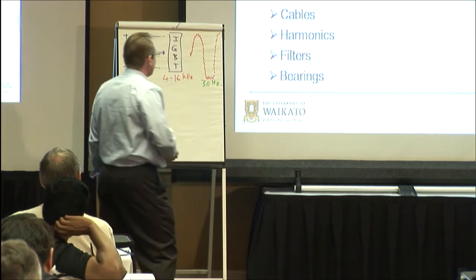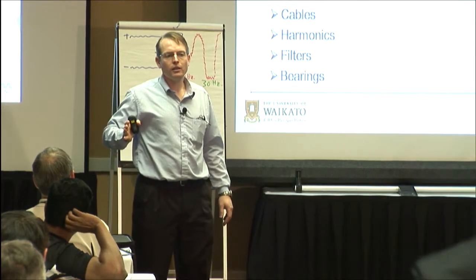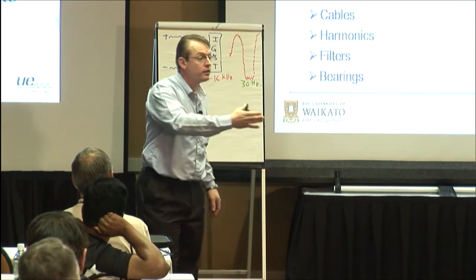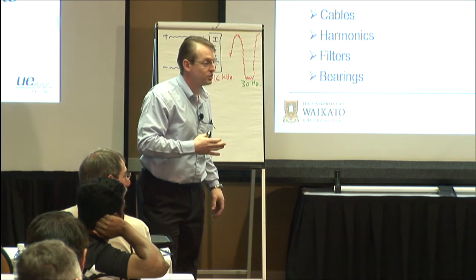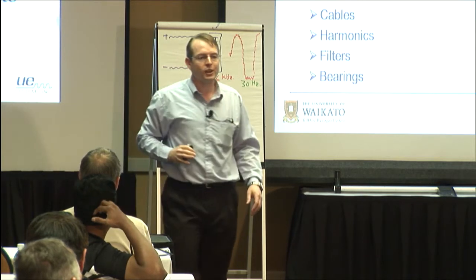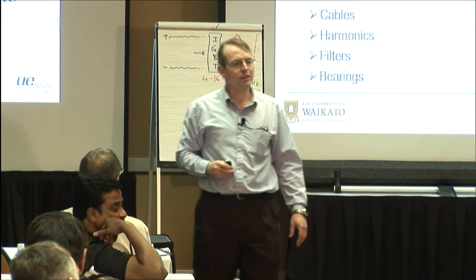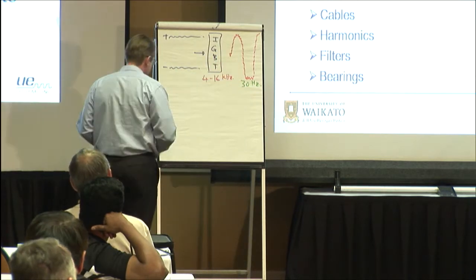As I mentioned, cabling to the VSD, absolutely important. What sort of cables need to be used? Does anyone know? Shielded cables. Shielded cables, yeah. And you mentioned your VSD's got some nice filters on there, dealt with the harmonics. Absolutely, and that's what they're for. Okay, I want to talk for a minute about this discharge on the bearings.